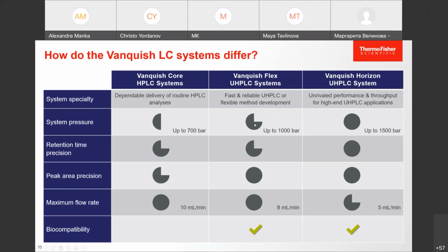And here in this comparison, you see these circles, just to compare those. Retention time precision is of course really good with all the systems, but it's best on the Vanquish Horizon. Same for peak area precision. What you see also here is the flow rate maximum. So the Core can go up to 10 mL, while the Flex goes up to 8 and the Horizon up to 5. And in terms of biocompatibility, for the Flex and the Horizon the system fluidics are made of MP35N, which is a biocompatible alloy, while the Vanquish Core system is made out of stainless steel and thus not biocompatible.